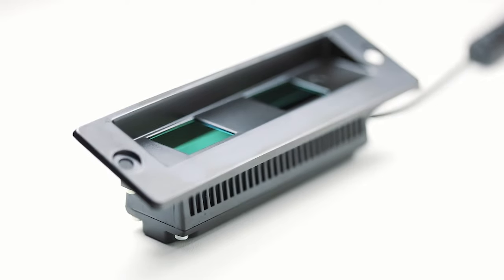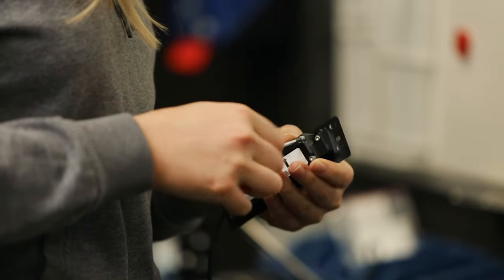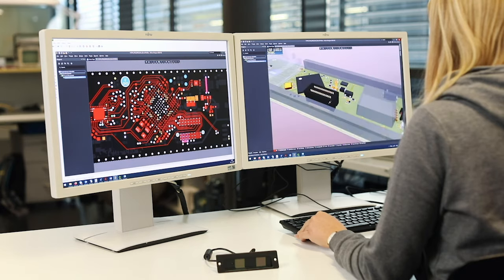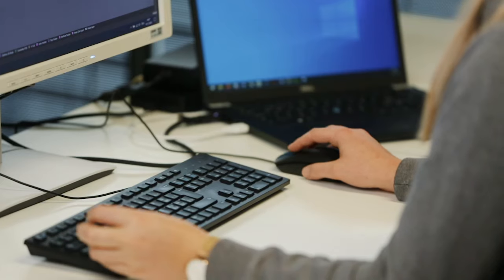A single multi-color indicator LED shows the status of the sensor. The Capsafe 3D fulfills the code requirements for many different types of entrance opening geometries. A single Capsafe 3D sensor version supports left, right, and center opening entrances, entrance heights to 3 meters, and entrance widths to 1.37 meters. A robust mounting solution is standard using the flush mount bracket included with the sensor. Optionally, customers can choose a stainless steel back-of-transom bracket. Regardless of which bracket is used, the sensor only extends a few millimeters below the transom and is protected from being struck by equipment entering the elevator cab.